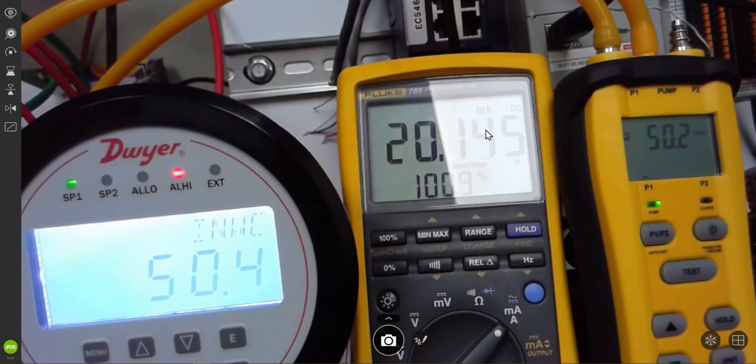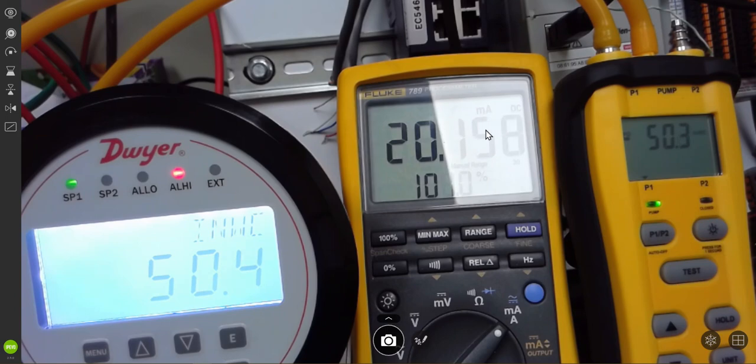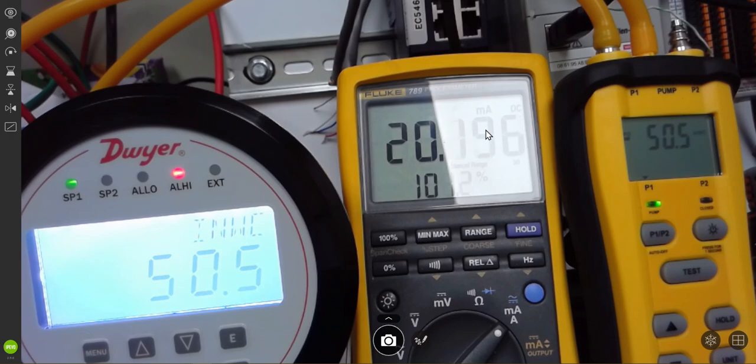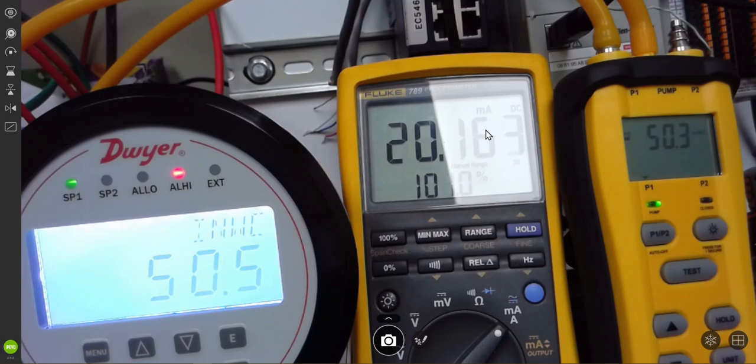So we're going to go with, like I said, we're not really so much worried about precision. We're not going to fudge this. We just want to make sure it's close. One inch of water column, somewhere 5%, 10%. This one is well within spec. So we're going to call this calibration done.